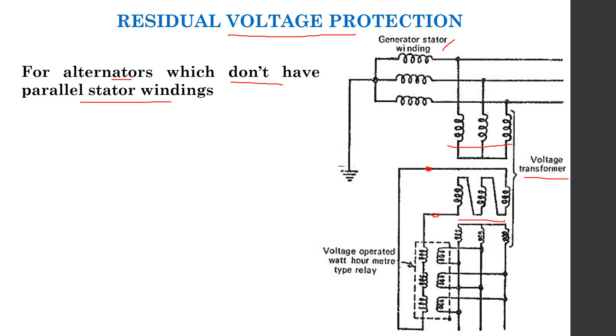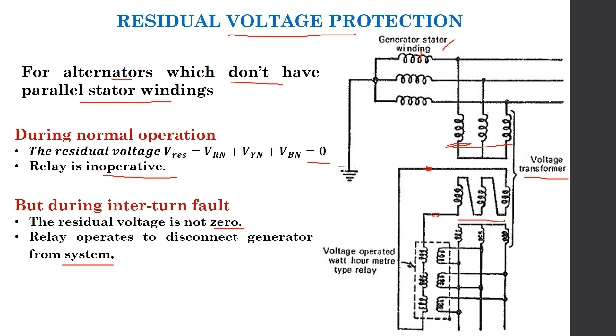During the normal operation, the residual voltage fed to the relay is equal to 0, and therefore the relay remains inoperative in this case. Whereas when an inter-turn fault occurs, then this residual voltage no longer is equal to 0, and therefore the relay operates to disconnect the generator from the system. Suppose an inter-turn fault occurs on this phase of the stator winding, then the primary voltage of the voltage transformer associated with that phase will reduce, and as a result the voltage transformer secondary will also change, and therefore the residual voltage will no longer be equal to 0, and thus the relay will operate and will disconnect the generator.